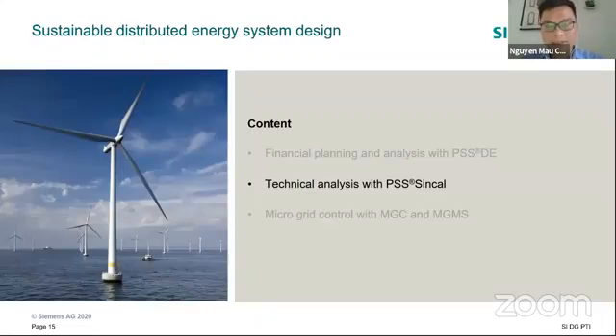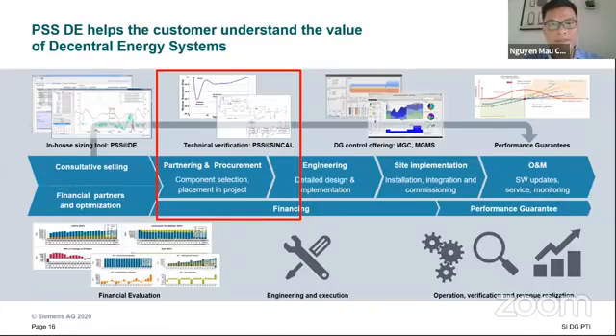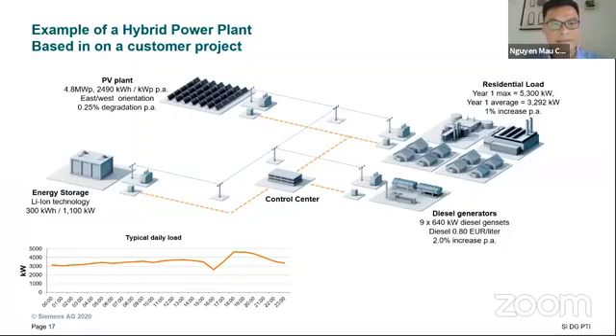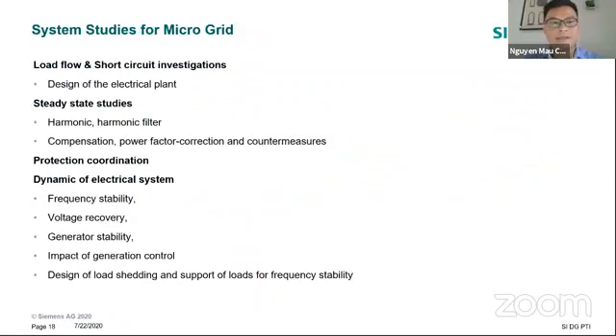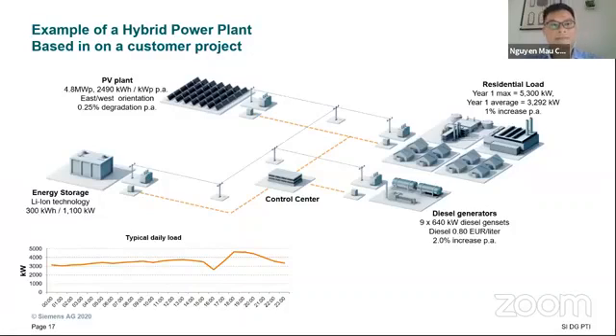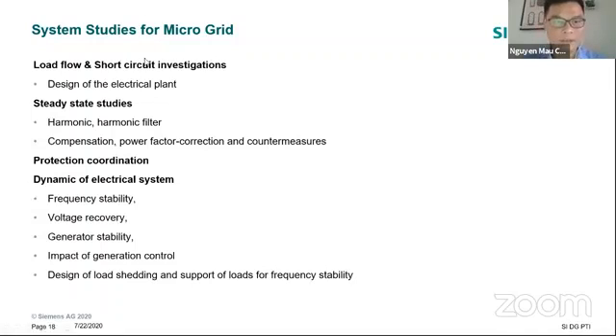So that's why the next step, we need to go to the technical analysis with PSS Sincal. This is the second step here. And here we have the network, and this network must be investigated in the technical study. So the first is the load flow and short circuit investigation to design the electrical plant. Let's say how big the transformer should be, how to size the cable, optimize the length of the cable, the cross section of the cable, and so on. Also calculate the short circuit to select the circuit breaker or for the protection coordination.